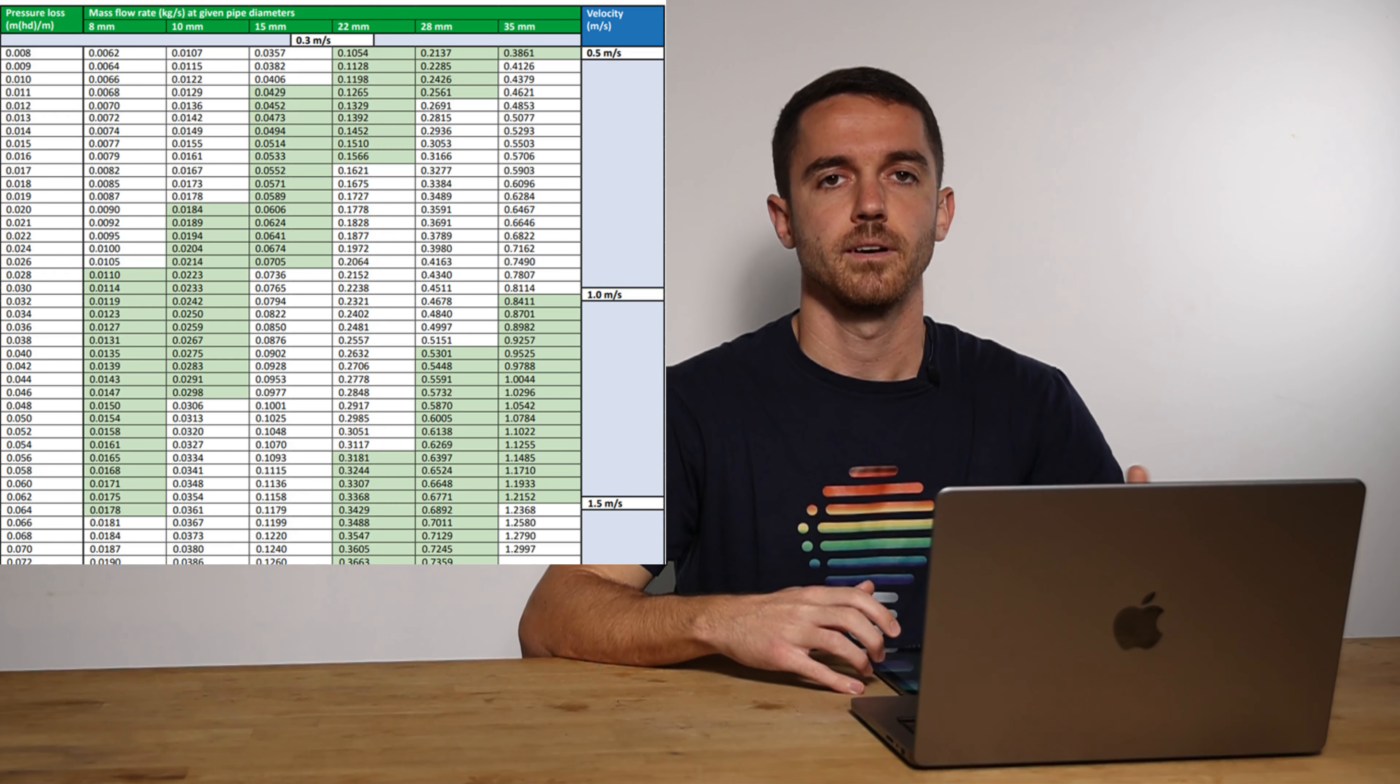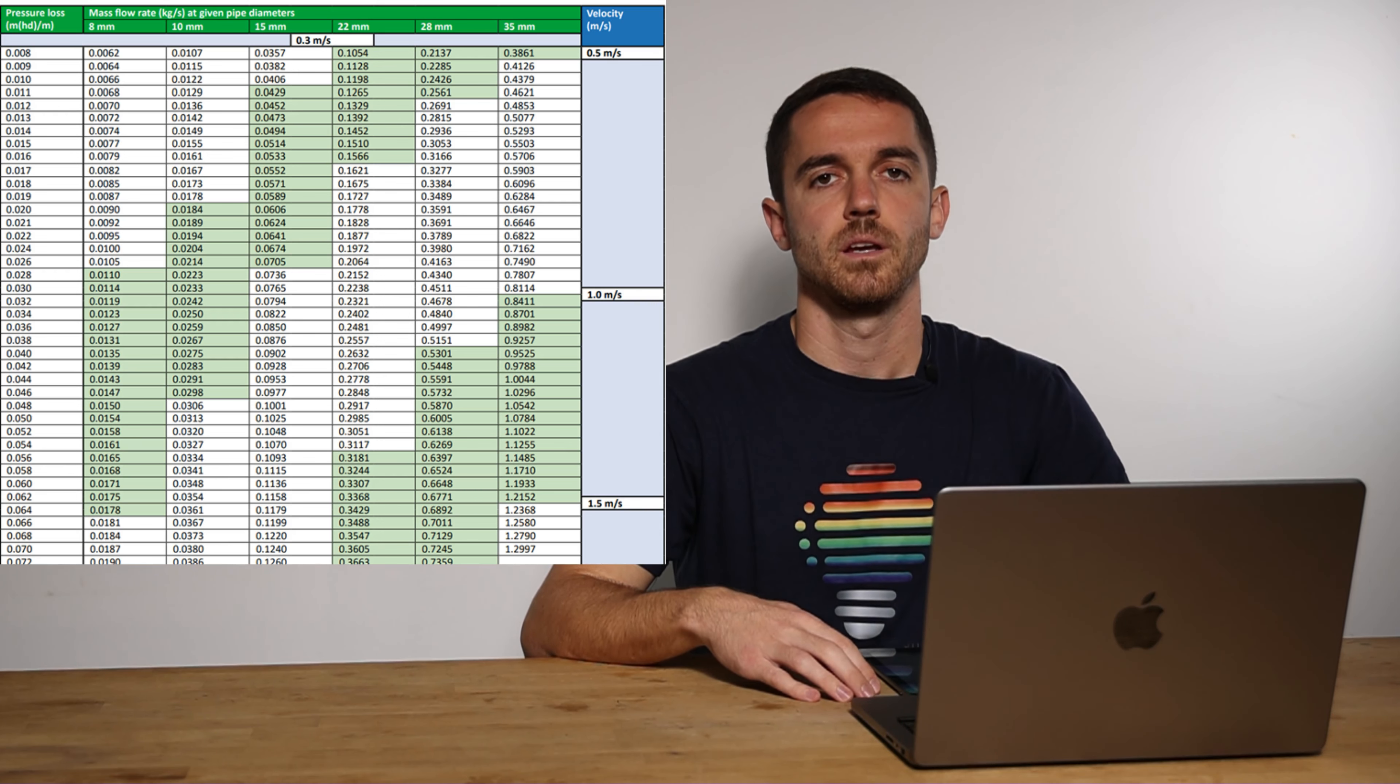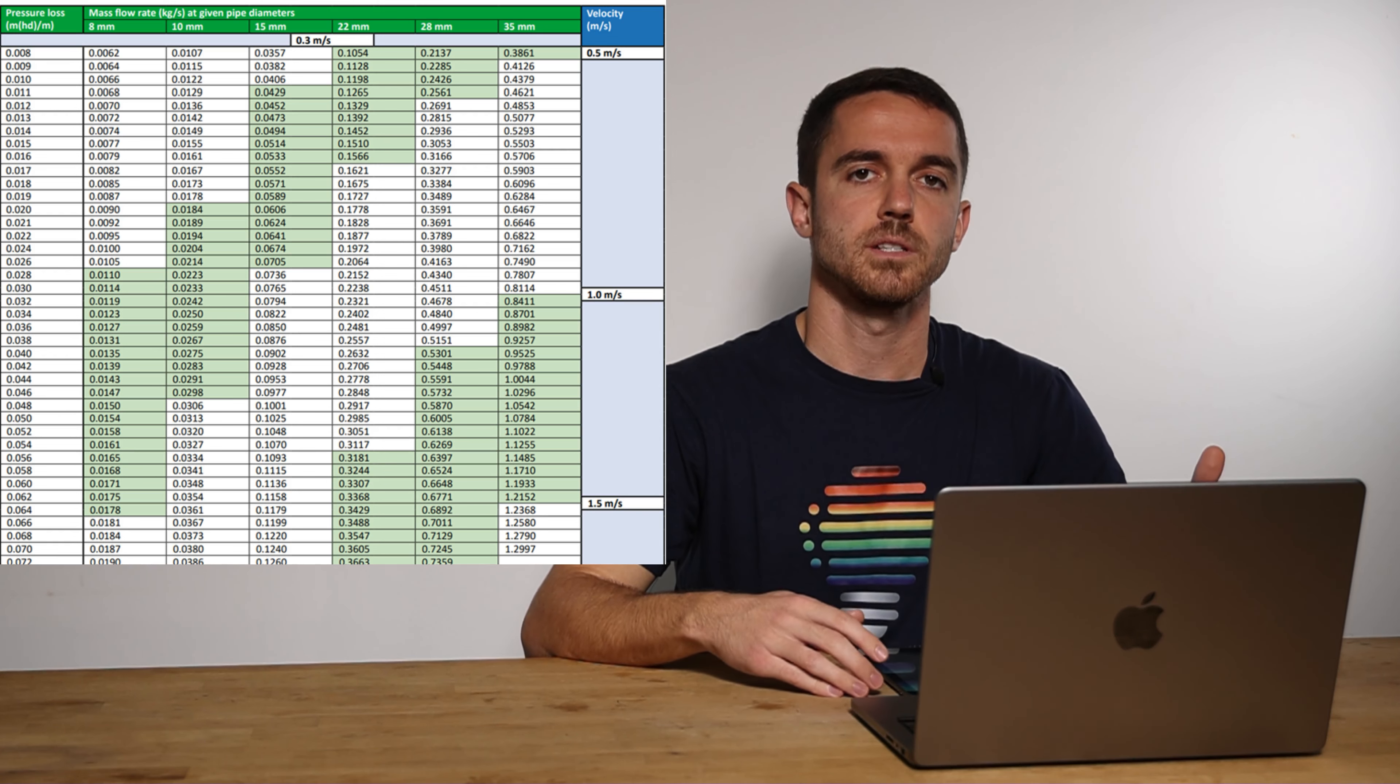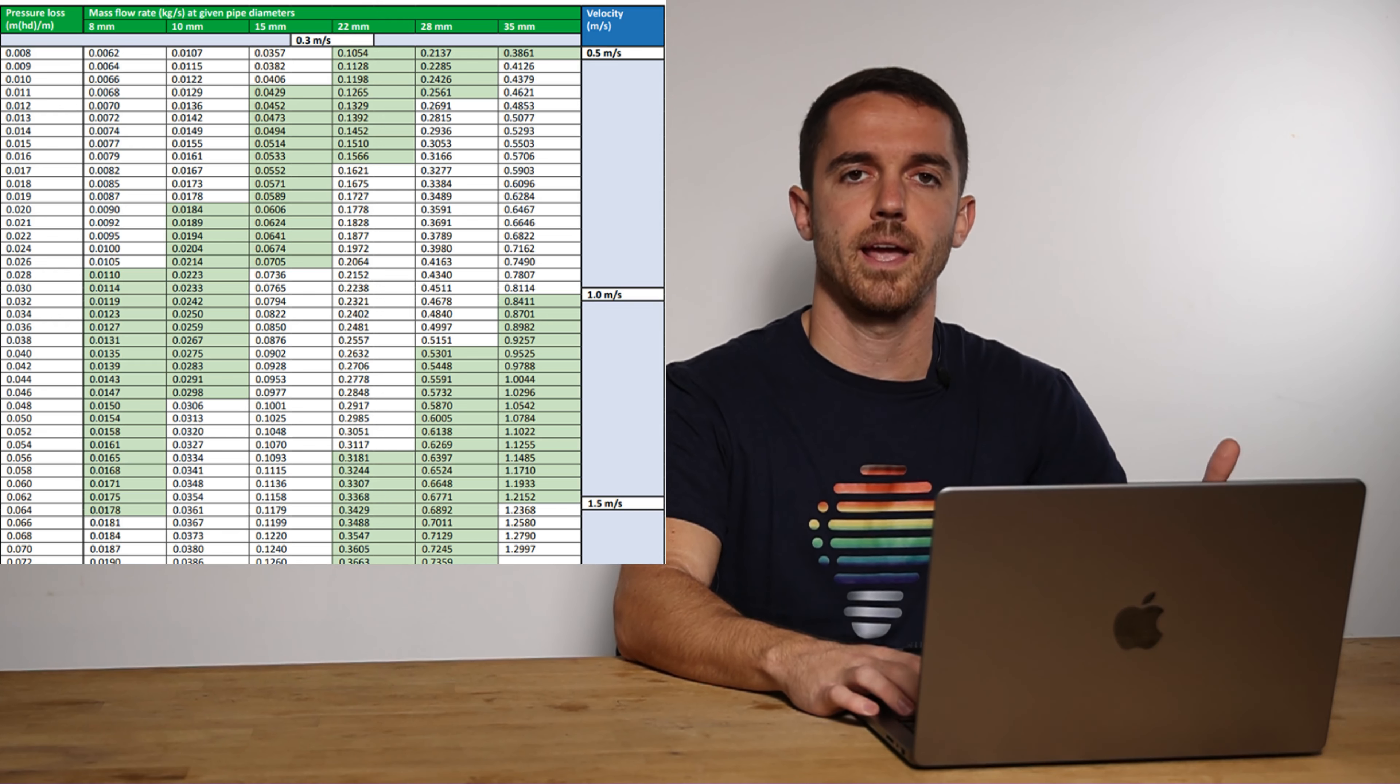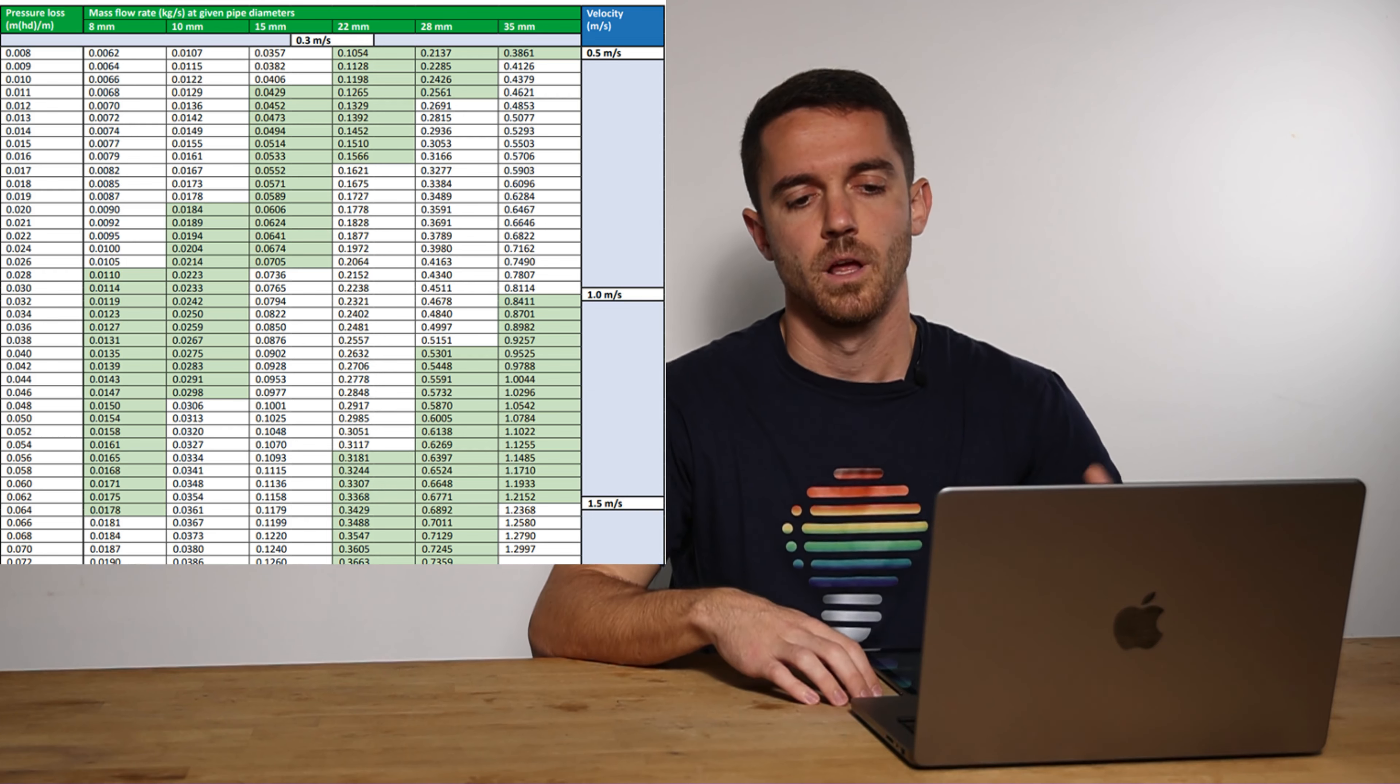We have guiding tables. In this table, we can see what is the pressure drop and what is the velocity for each pipe size. And our aim is to have this velocity around one meter per second.